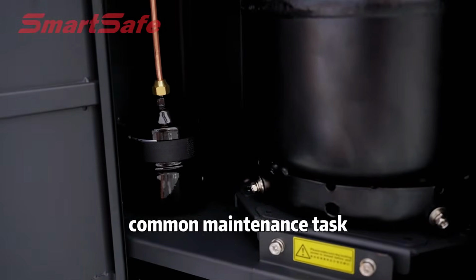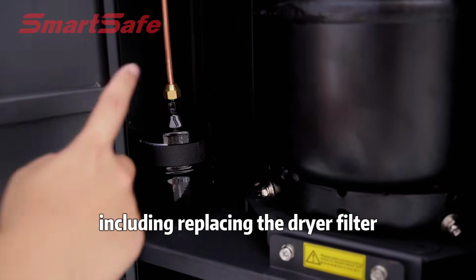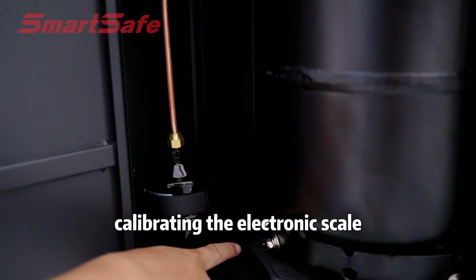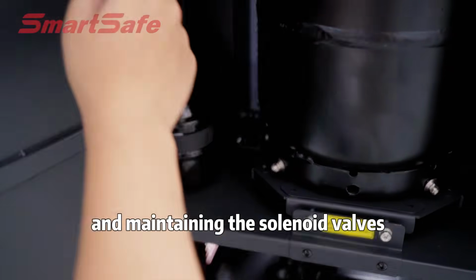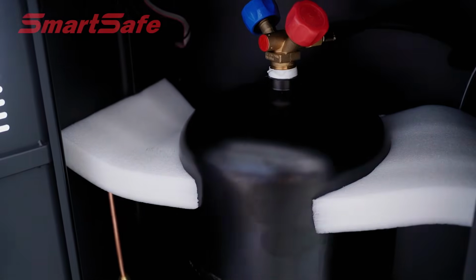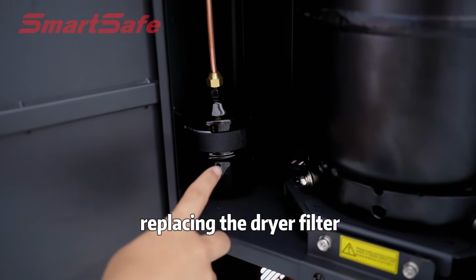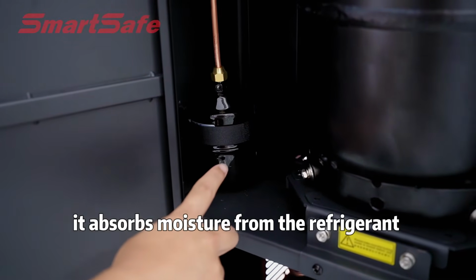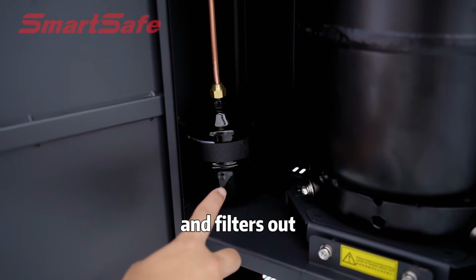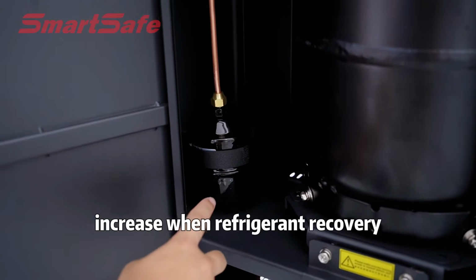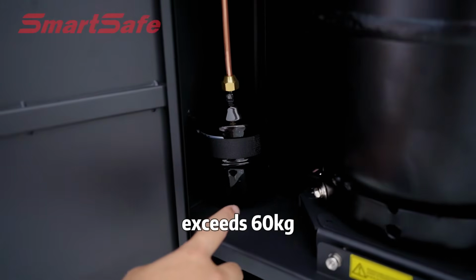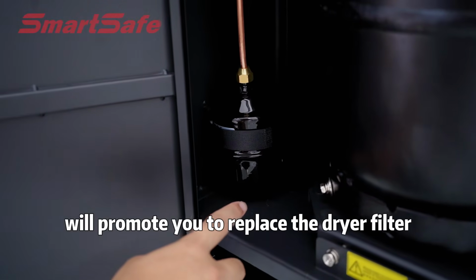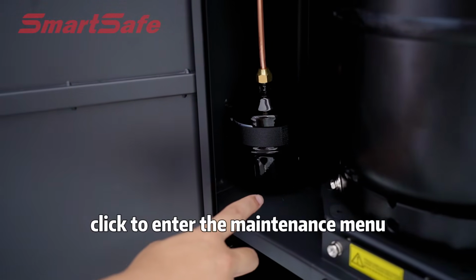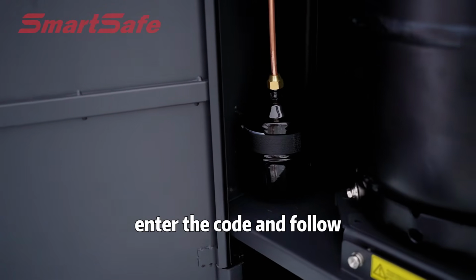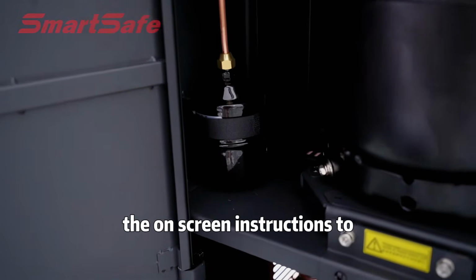Now let's talk about common maintenance tasks, including replacing the dryer filter, calibrating the electronic scale, and maintaining the solenoid valves. First, the most common task, replacing the dryer filter. It absorbs moisture from the refrigerant and filters out impurities. When refrigerant recovery exceeds 60 kilograms, the system will prompt you to replace the dryer filter. Click to enter the maintenance menu, enter the code, and follow the on-screen instructions.